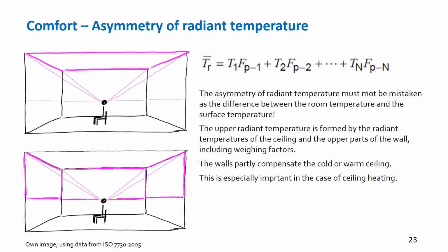So if you're sitting in such a room and the facade areas are at room temperature and only the ceiling is warmer or colder, then it's a weighted average of the radiant temperature which is counting, and it's the weighted average of the radiant temperature below your head which is counting, and this difference has to stay between the limits, in these limits, and not the surface temperature against the room temperature. This is a widely used mistake, and it's important to correct this. And the sun, again, is a good example. The sun has a radiant temperature of 6,500 degrees, and we're really lucky that it's only so small in this angle, in this room angle. It's only a tiny spot, and the rest is the -10, -20 degree cold sky. And the mixture of both gives a nice radiant temperature above our heads.